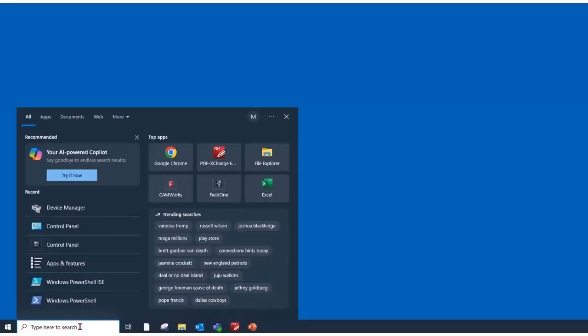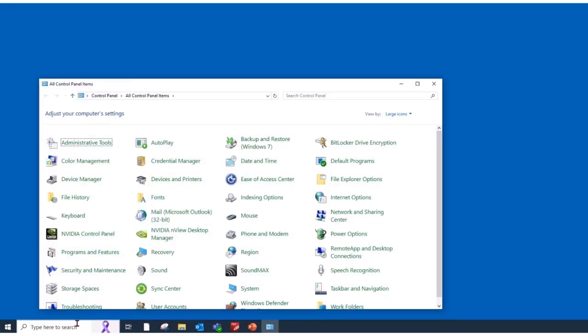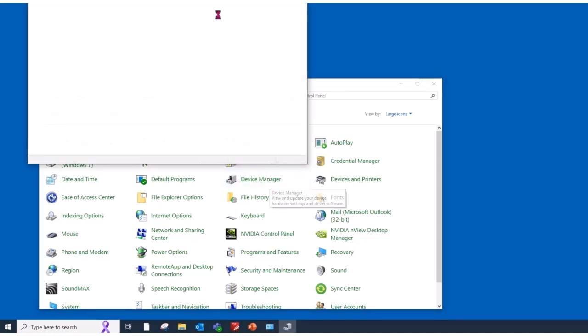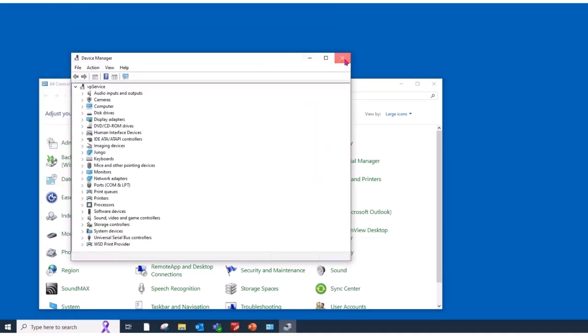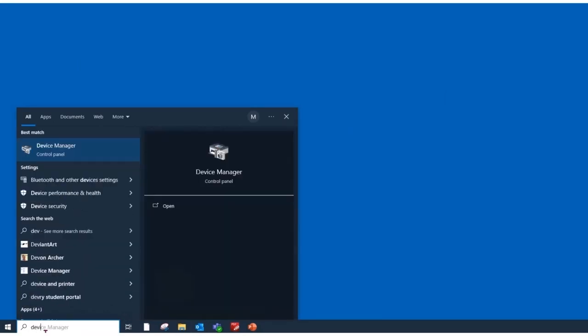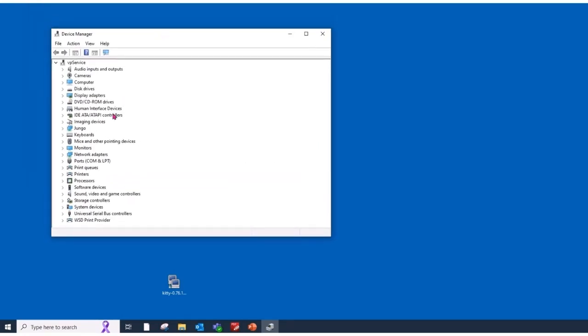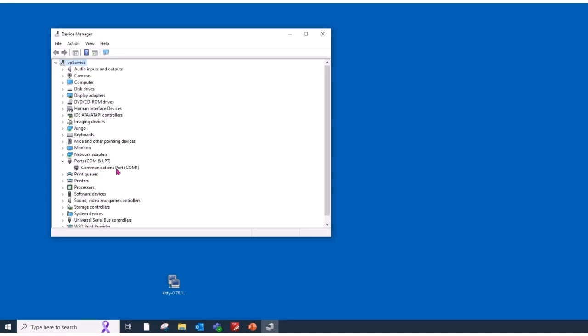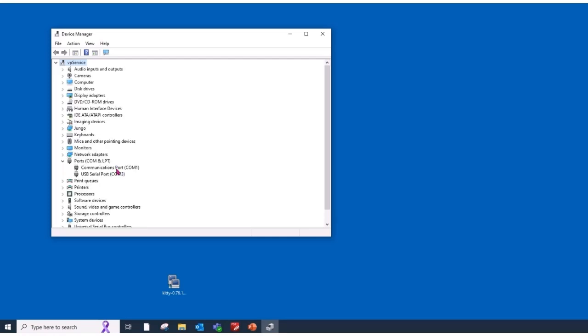Before you can communicate with the panel with your laptop, you need to set up your COM port settings. You can go to Control Panel then Device Manager or you can simply type in Device Manager down below in the search bar. One thing you'll have to look at is your COM ports. This computer has a hard COM port built into it. Most computers now don't have that anymore, so you have to plug in a converter or a USB serial port. And you'll want to know what COM number gets assigned to that device.